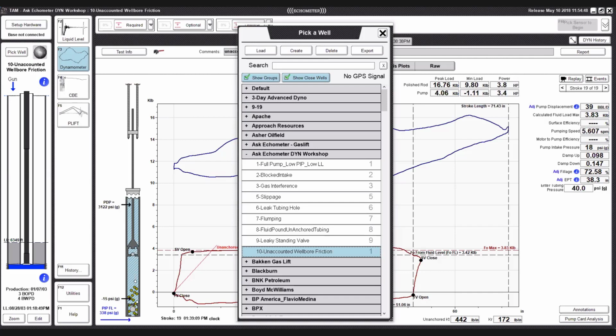It's a total. It's the OD of the plunger subtracted away from the ID of the barrel. So it's the total clearance. So it's not just the minus clearance on the plunger, but you have to add the plus clearance on the barrel. Yes. So for his practical example, it would be 5,000ths, 0.005 inches for the input in the software. 0.003 plus 0.002 would be 0.005. That's what you type into the clearance.